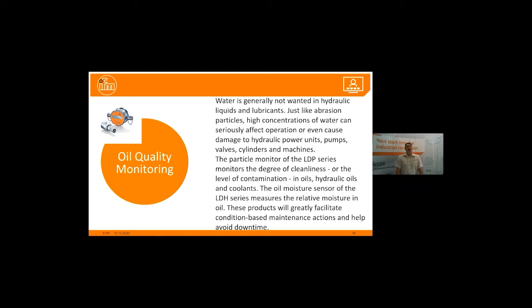Water is generally not wanted in hydraulic liquids or lubricants. Just like abrasion particles, a high concentration of water can seriously affect operations or even cause damage to hydraulic power units, pumps, valves, cylinders, any machine. The particle monitor of the LDP series monitors the degree of cleanliness or the level of contamination in the oil, hydraulic oils, or coolants. The oil moisture sensor of the LDH series measures the relative moisture in oil in a percentage value. These products will greatly facilitate condition-based maintenance actions and help avoid downtime.